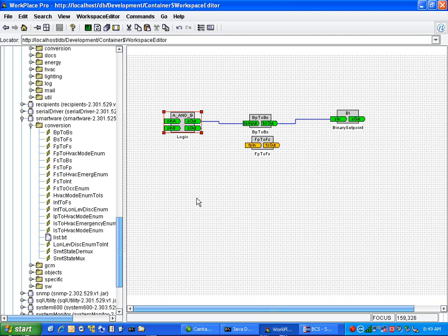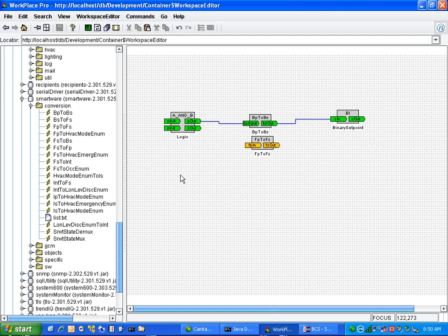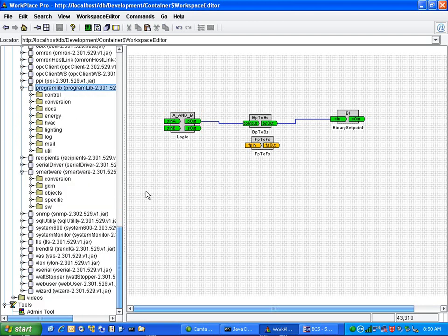It depends on which object you're using. If you want to send an input, a value down to the controller, it depends if you're using the analog set point object or the analog set point priority object. The priority one is going to have the priority array, and the plain analog set point is going to have just a status input. So oftentimes we have to convert it depending on what object it is that we're linking and sending it down to. Like anything, the more you work with it, the more you figure out. I've run into situations where I've needed to know how to get around this. Exactly, that kind of thing.